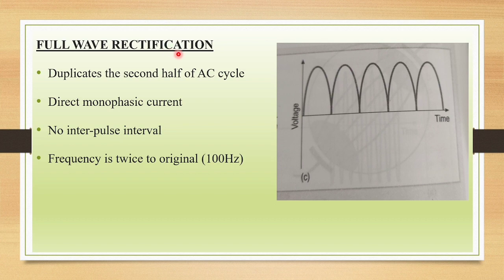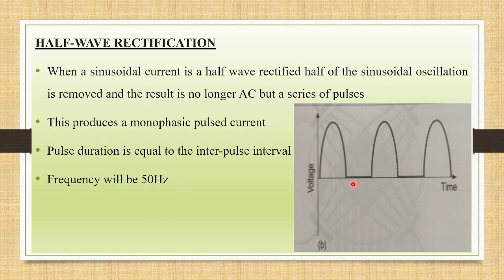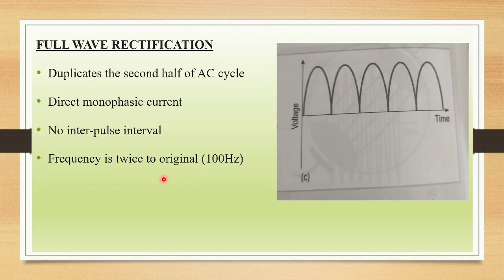In full wave rectification, it duplicates the second half of the AC cycle. This is known as direct monophasic current. There will be no interpulse interval between the pulse periods, and the frequency is twice the original. So in half wave rectification the frequency is 50 Hz because of the presence of interpulse interval. In full wave rectification, since there is no interpulse interval, the frequency is twice normal — that is 50 into 2, which is 100 Hz.